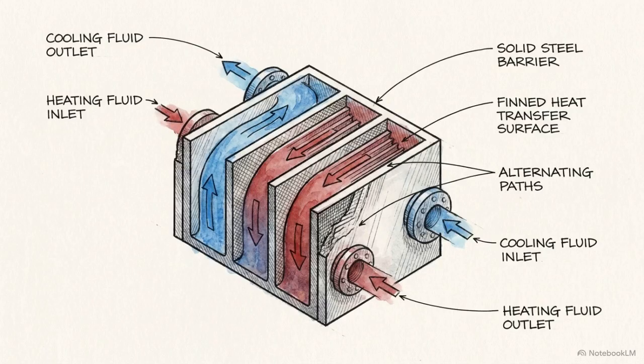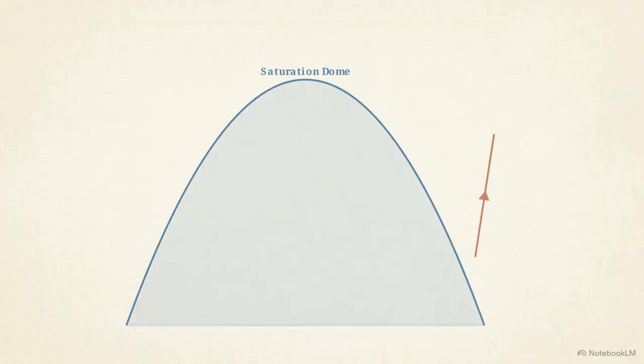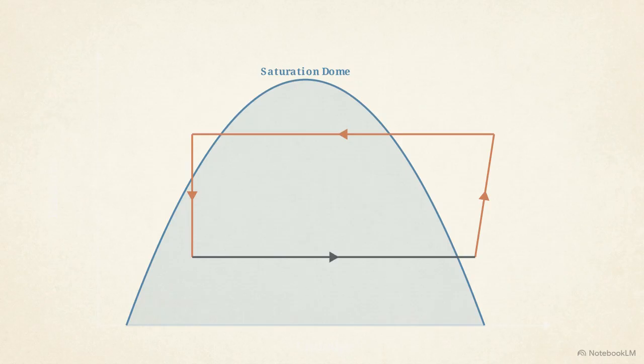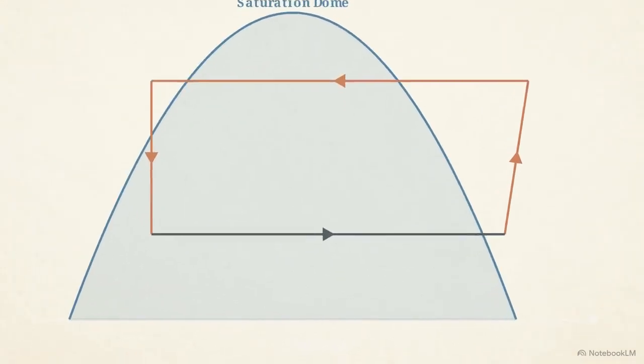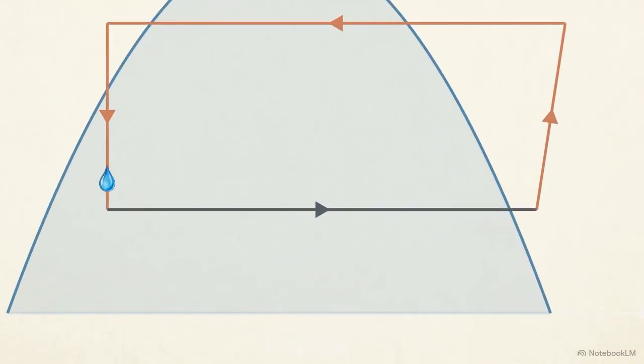This is the physical bridge of the chiller unit, where the primary and secondary loops meet, exchange heat, but never physically mix. This pressure enthalpy diagram outlines the secondary loop, which uses a phase change refrigeration cycle to capture the heat from the primary fluid and mechanically relocate it. Inside the heat exchanger, a liquid refrigerant absorbs the thermal energy from the primary coolant. The heat causes the refrigerant to boil, vaporizing it into a low-pressure gas.